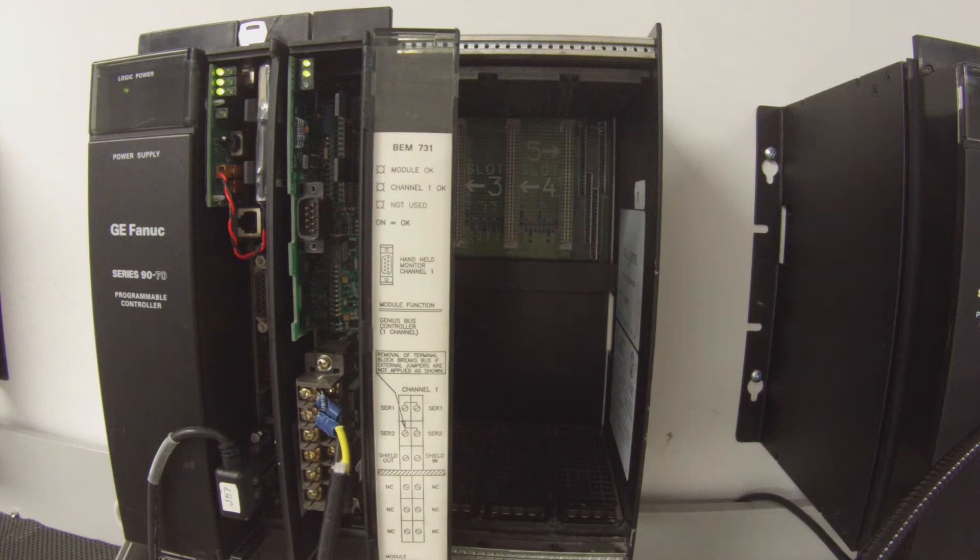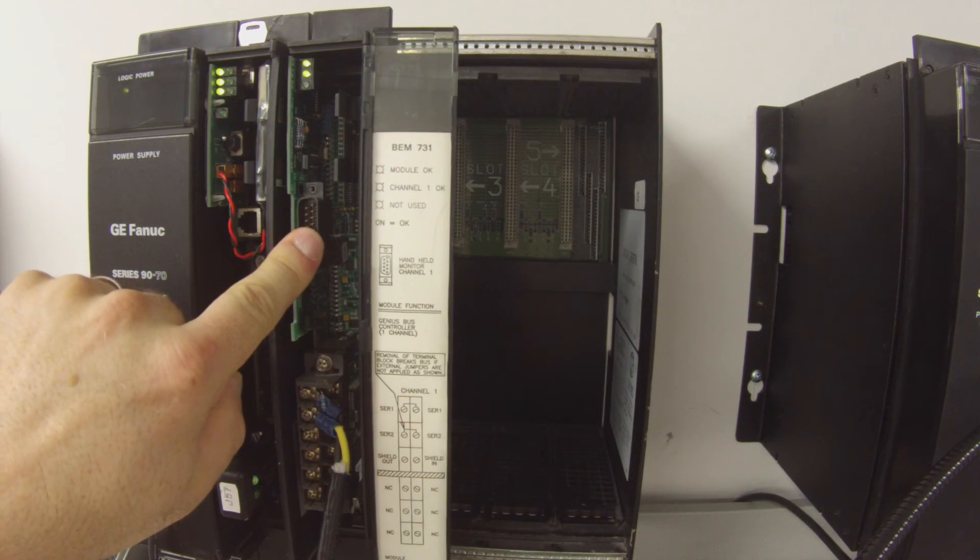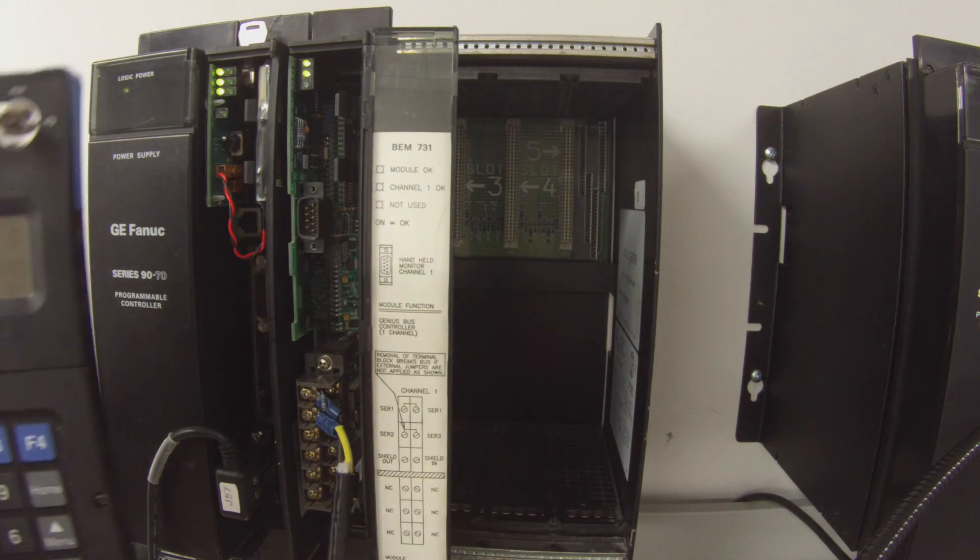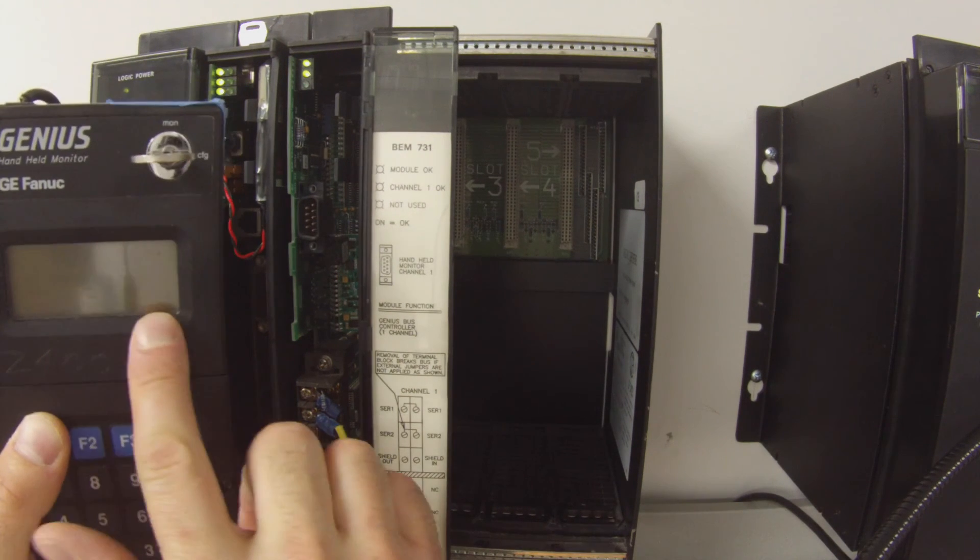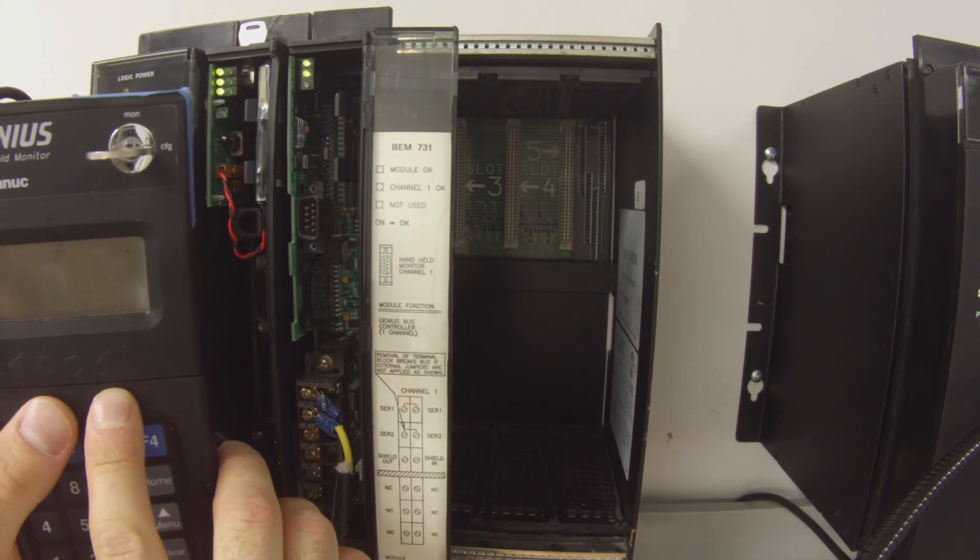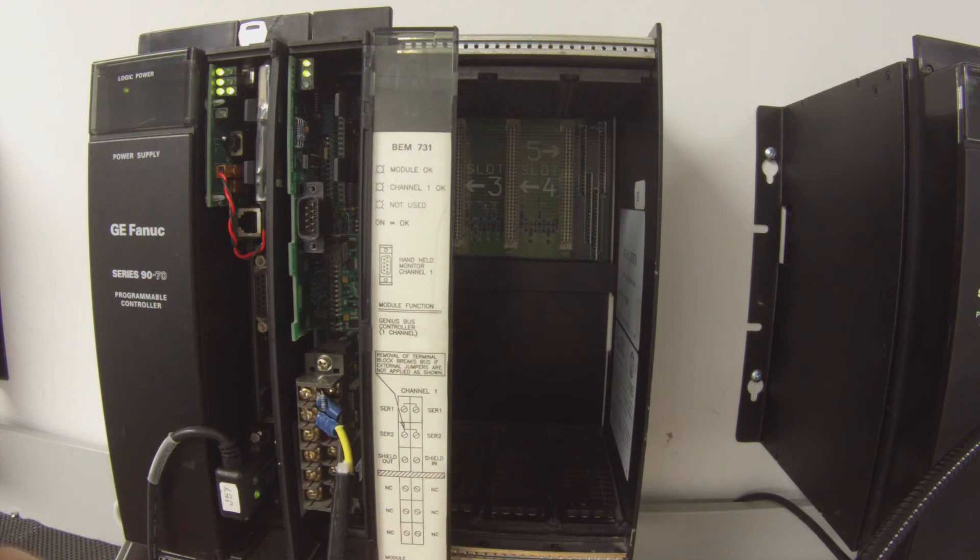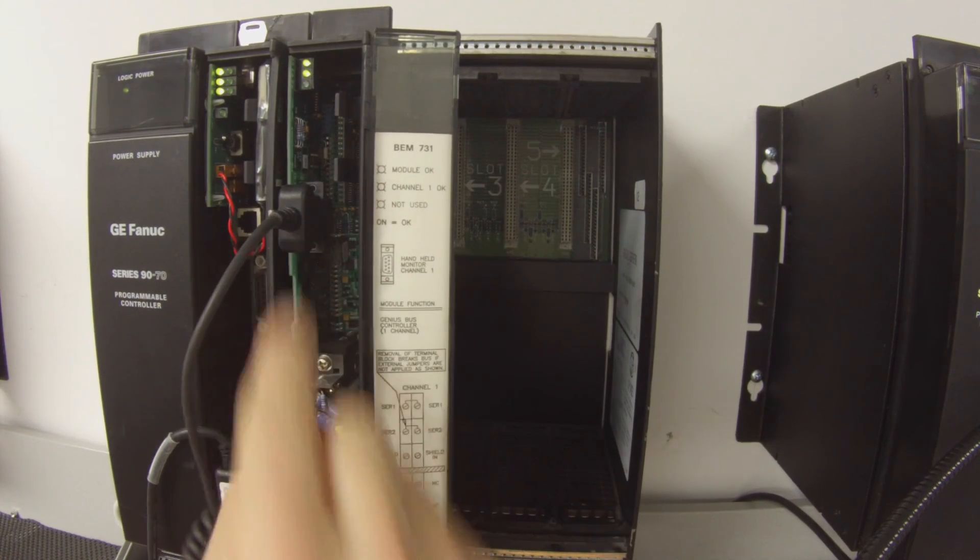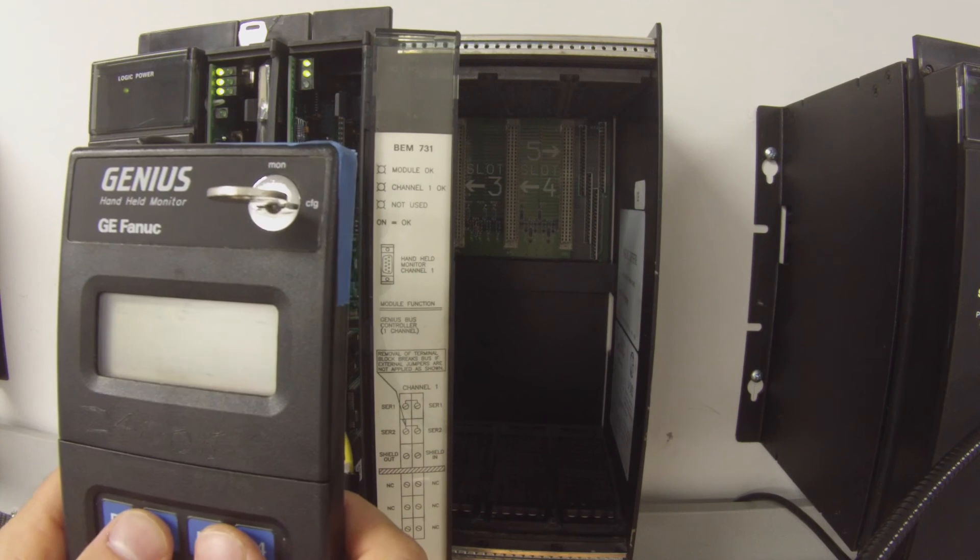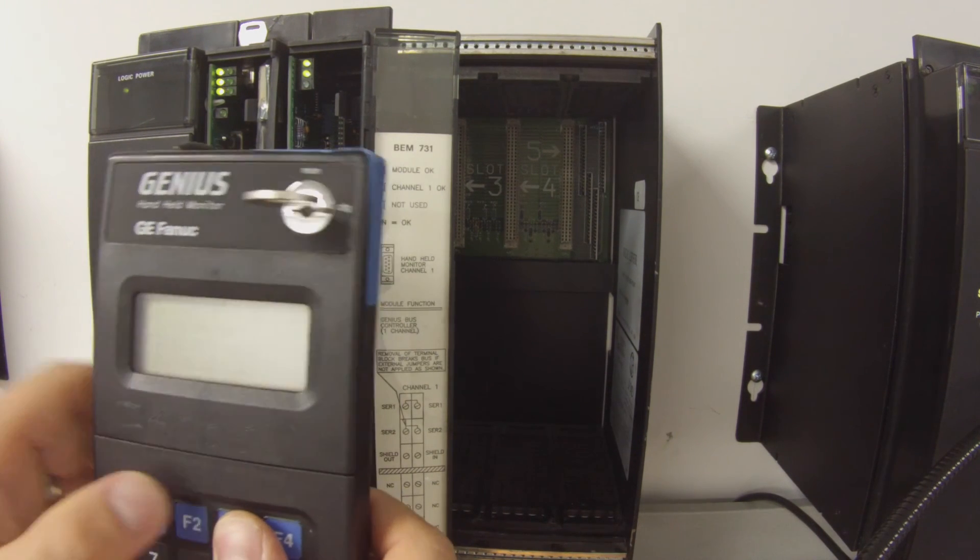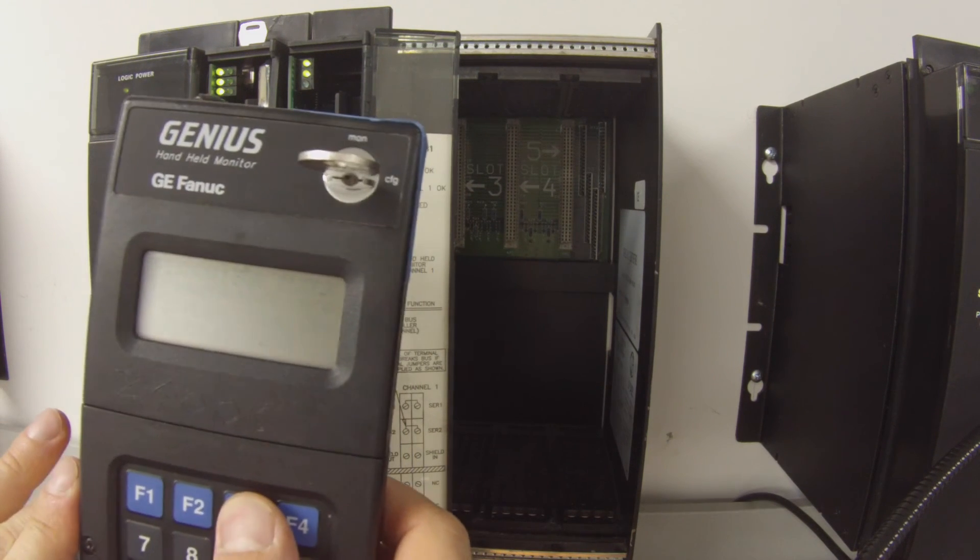Number two is the handheld monitor to be able to go in here and monitor. And there's a simple way to test that. And I have here an IC660 Genius HHM501. So it's an IC660HHM501 handheld monitor. So I'm going to go ahead and plug this in securely. And then if you look on the monitor, I'm going to turn it on. What I want to do is hit OK, Analyze, F2, and then F3, Block Bus Status.